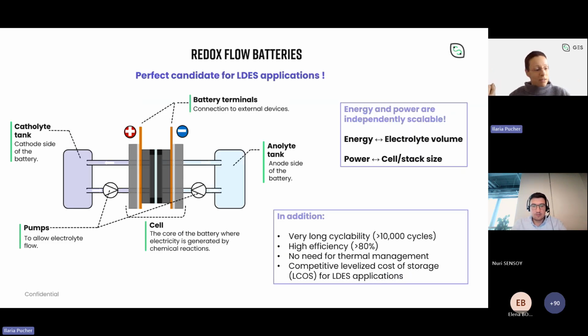So what are redox flow batteries? They are batteries in which energy and power are decoupled, and therefore independently scalable. Energy is defined by the volume of the usually liquid electrolytes in which redox couples are dissolved, while power is defined by the cell area or stack size where redox reactions occur. In addition, redox flow batteries usually have a very long cyclability, more than 10,000 cycles. They have a pretty good energy efficiency, more than 80%, and usually don't need thermal management.